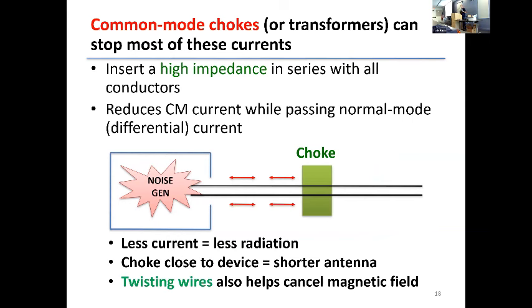So what do you do? The first thing is to try to reduce the common mode current. If you reduce the current, that means less noise signal. This is done by inserting some kind of high impedance, which reduces the current, and reducing the current reduces the amount of signal. So our intent is to reduce the common mode current without affecting the normal mode current.